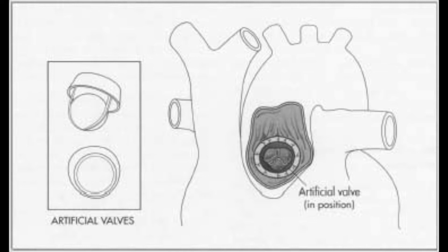Once the sewing cuffs are completed, a specialized heating process is used to form the cuffs around the valve. The valves are then mounted into a rotator assembly. Once the valves are made, they are steam sterilized in a double plastic container. This is step four. Next, a biological indicator is used to test for bacteria. If none are present, the valve is then packaged.